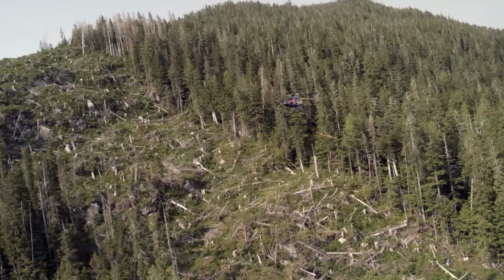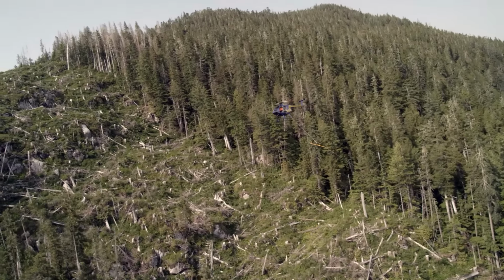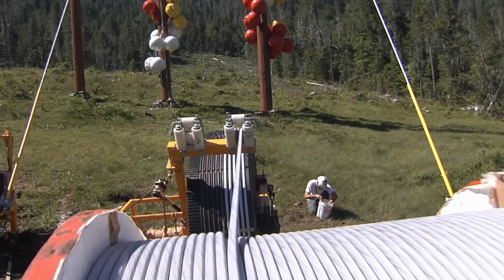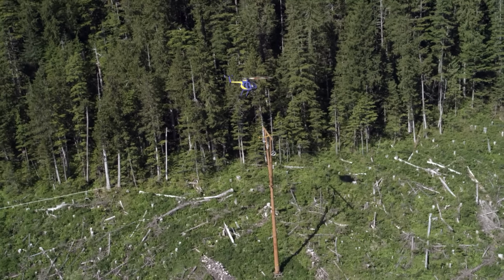The lead end of the sock line is attached to a device called a needle, and the other is kept tight as it's spooled off a reel on the puller at the other end. The pilot hooks up to one of the two eyes of the needle and then has to maneuver that while keeping it tight up and into each traveler wheel.